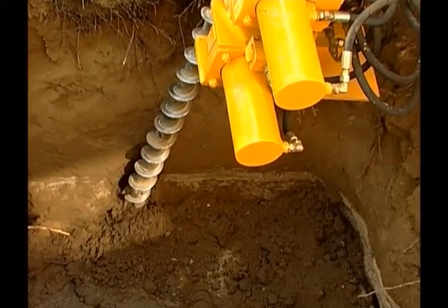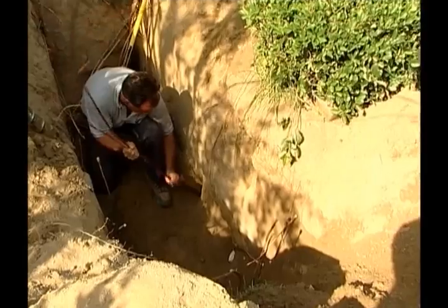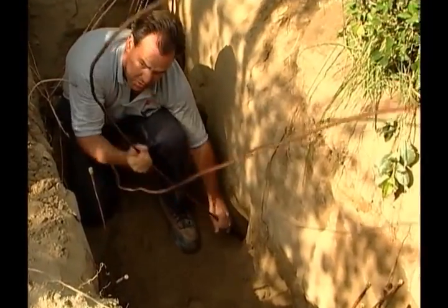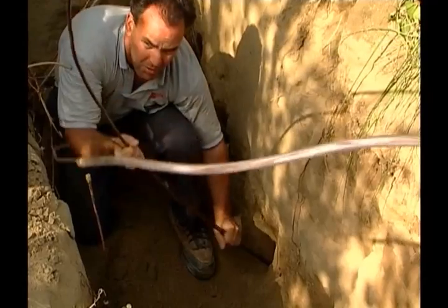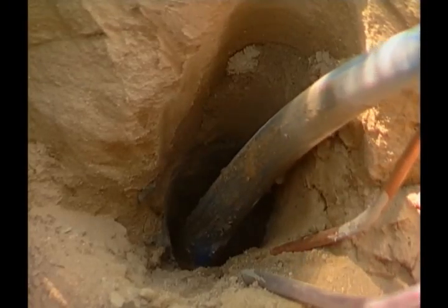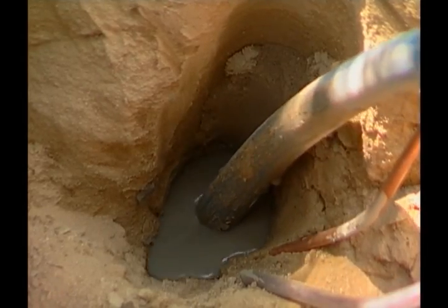In a direct exchange system, the loop is actually the refrigerant tubing in the system. That tubing has to be inserted into the earth, and it's essential that it makes contact with the earth for maximum heat transfer. After the loops are inserted in the hole, we grout that with a plasticized cement, which ensures that we have 100% contact around that loop for maximum heat transfer.